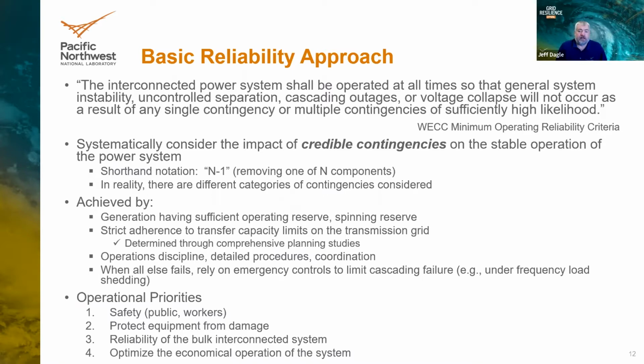The shorthand is n-1, removing one component out of the n components in operation. That's a shorthand, but in reality it's a bit more complex. The standards have 7 layers of contingencies that utilities assess, an agreed standard with different levels of severity that combines likelihood and consequence. A more likely thing shouldn't have any severe consequence. Things that are more rare, like a combination of events, you still want to consider for risk management purposes, and then you might allow some things like shedding load to protect the grid.